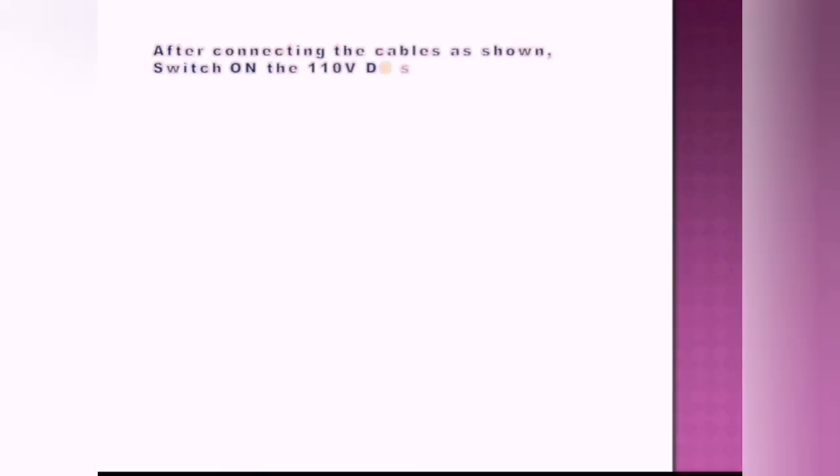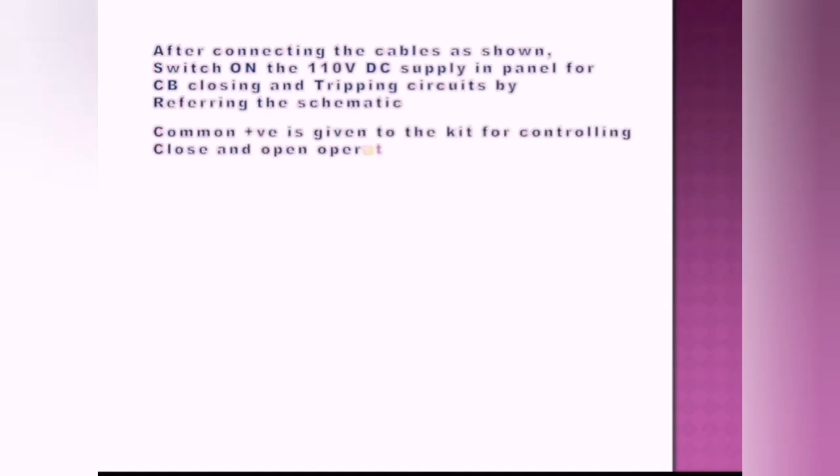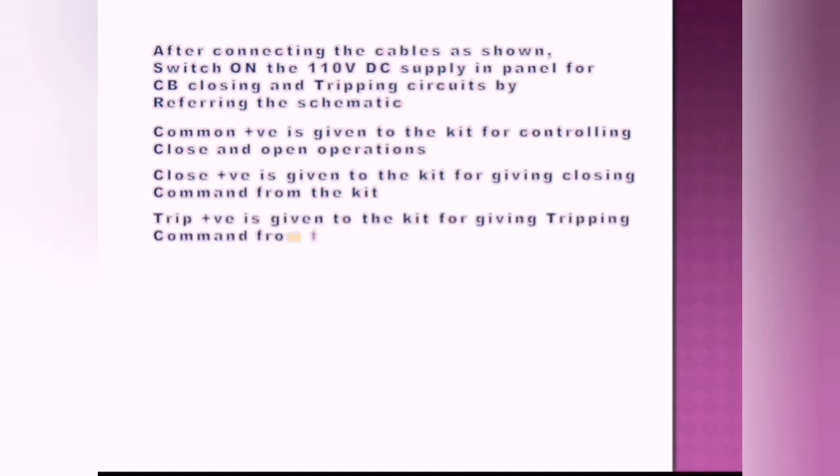After connecting the cables as shown, switch on the 110V DC supply in the panel for CB closing and tripping circuit. By referring the schematic, common positive is given to the kit for controlling close and open operations. Close positive is given to the kit for giving close command, and trip positive is given to the kit for giving trip command.